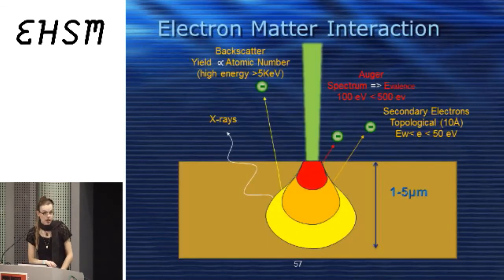So I'm going to go over a little bit of theory on how an SEM works. An SEM shoots a beam of electrons onto a tiny dot and then rasterizes that dot across the surface of your sample. And what happens when a beam of 5 to 20 keV strikes matter is you get these interactions. This is not a complete table of interactions, but these are the most commonly analyzed interactions.